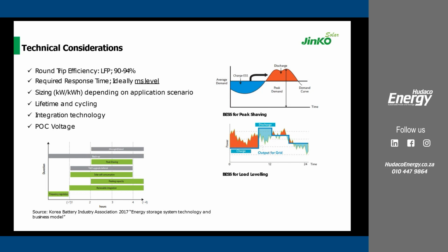In most of these scenarios, some customers or plants would actually prefer to have UPS systems, like rotary UPS systems, or more of an online UPS, to make sure there is ideally no power outage at any given time. You understand that online UPS is not quite cheap, it's quite expensive. So with the millisecond switching level, ideally less than 40 milliseconds or less than 20 milliseconds, we can still avoid the use of an online UPS.